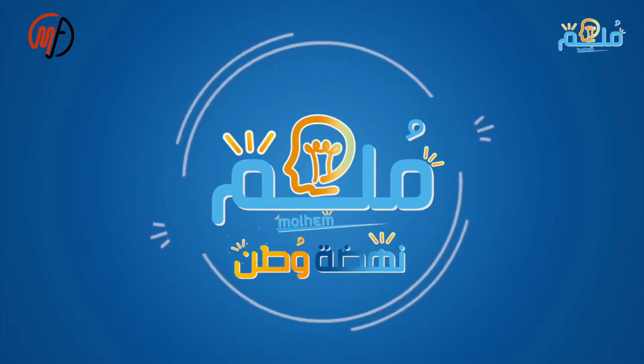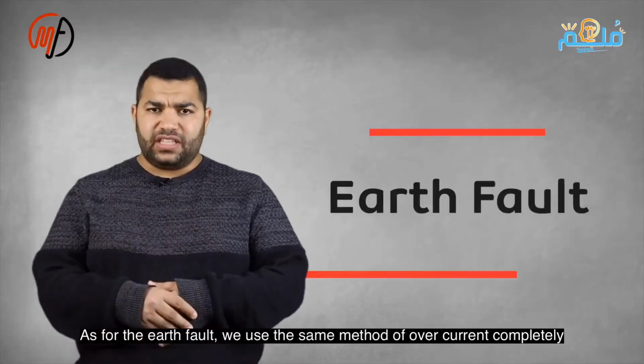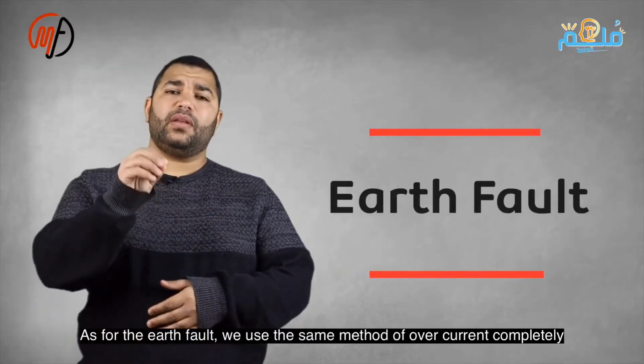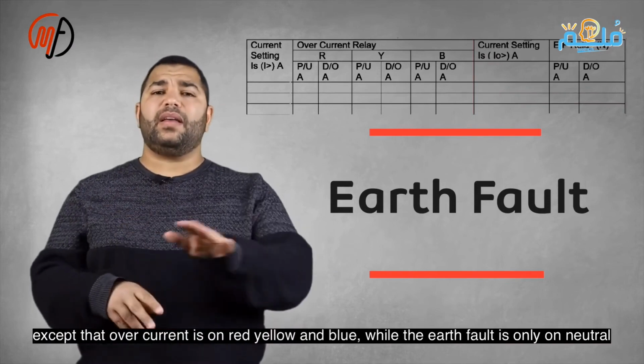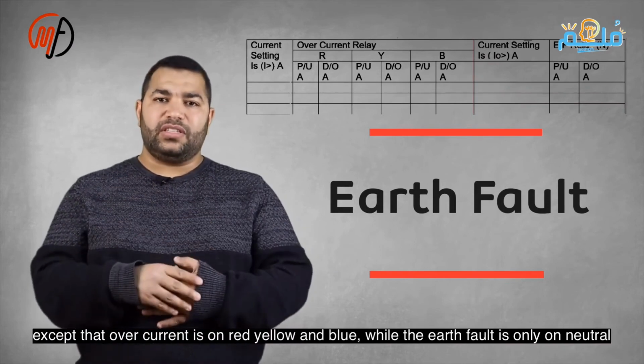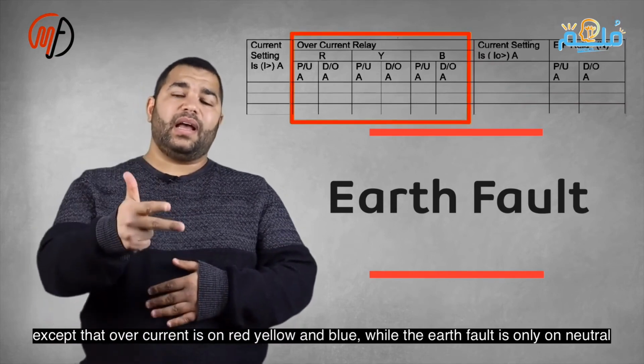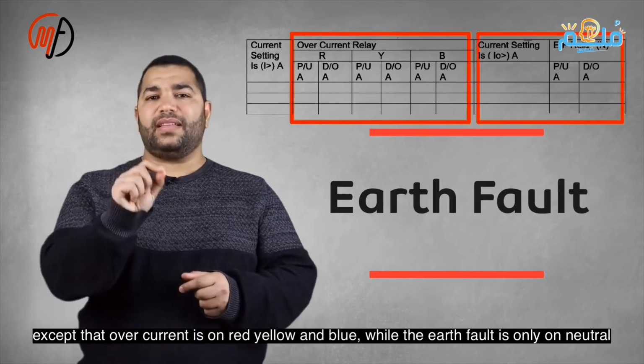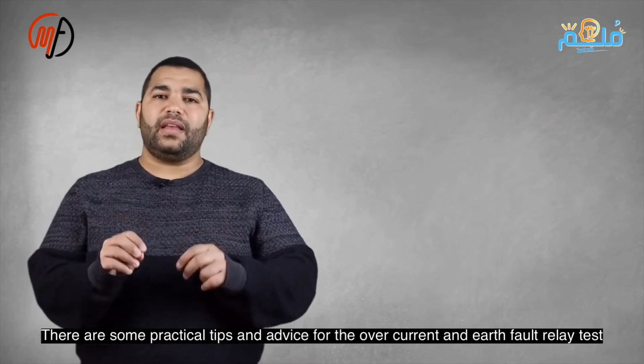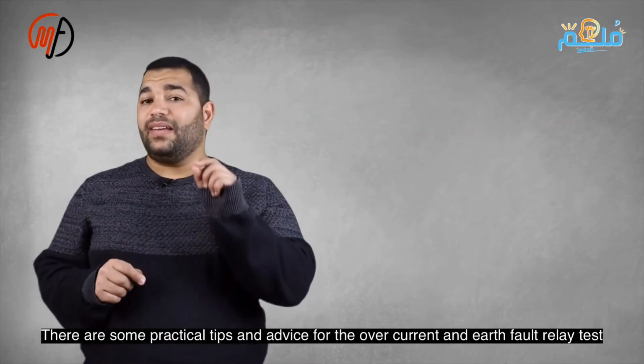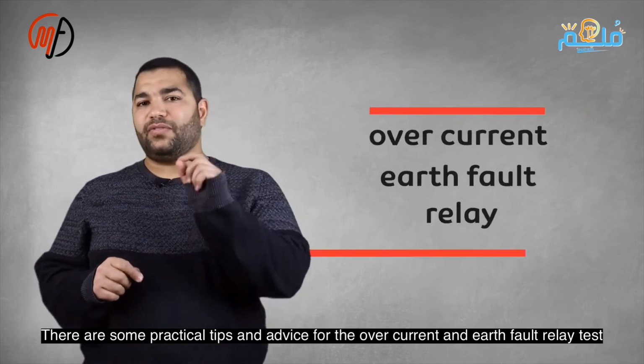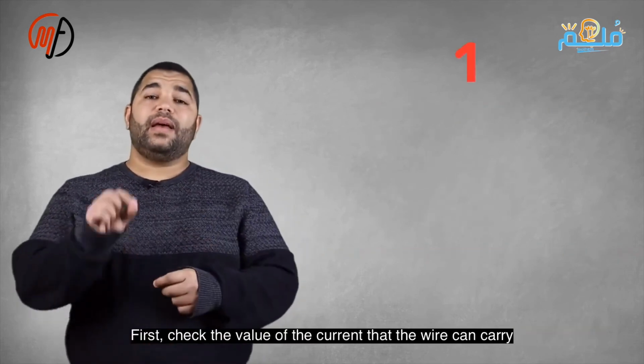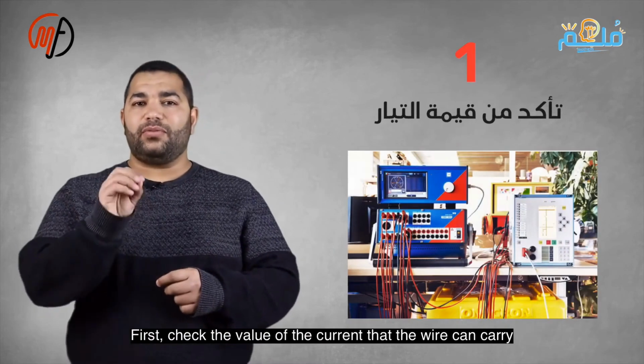For the earth fault, we use the same method as overcurrent. The difference is overcurrent is tested on red, yellow, and blue phases, while earth fault is on the neutral. Here are notes and tips for testing. Ensure the wire's current rating before injecting current to prevent damage. If a current higher than the relay's pickup doesn't trigger it, check settings to confirm it's a non-directional relay. Directional relays need voltage, current, and angle. Verify the output contact configuration matches for both protections. If the device won't inject current, check for open circuits with a continuity test.